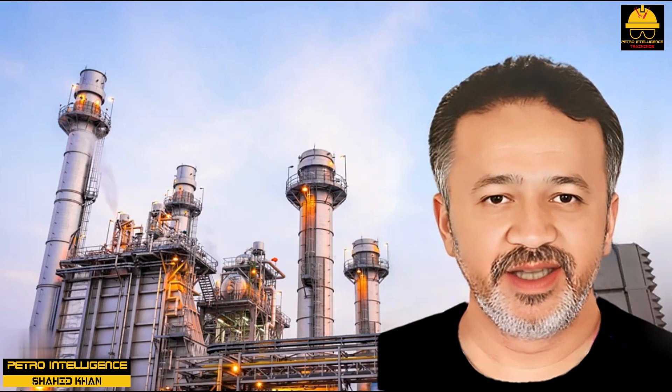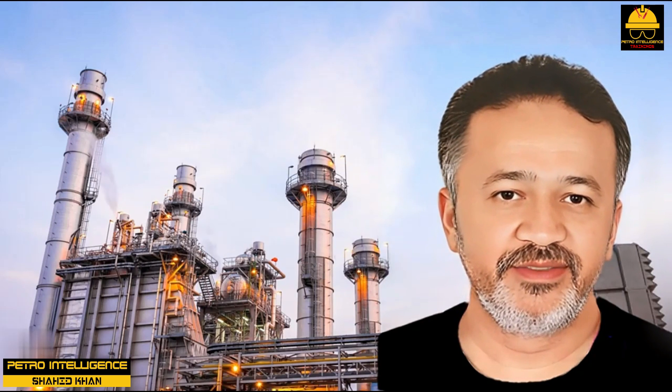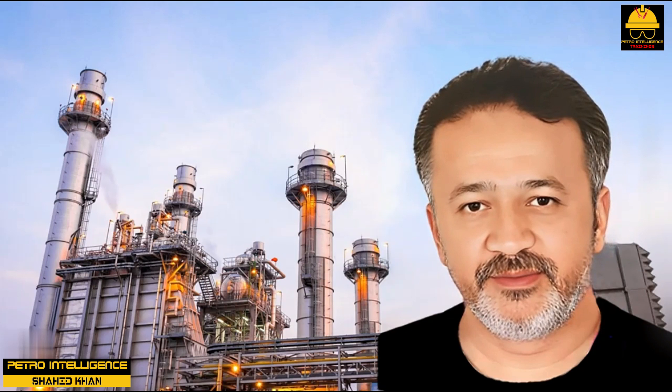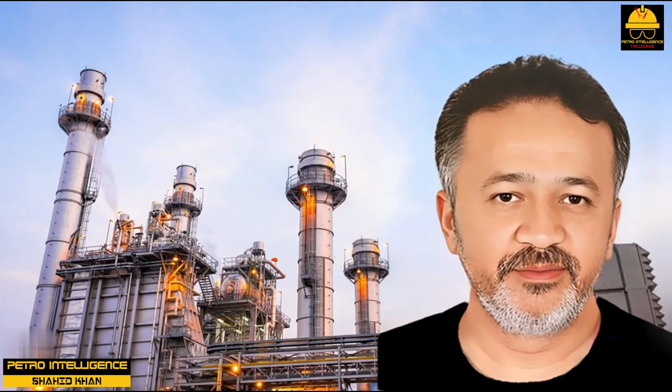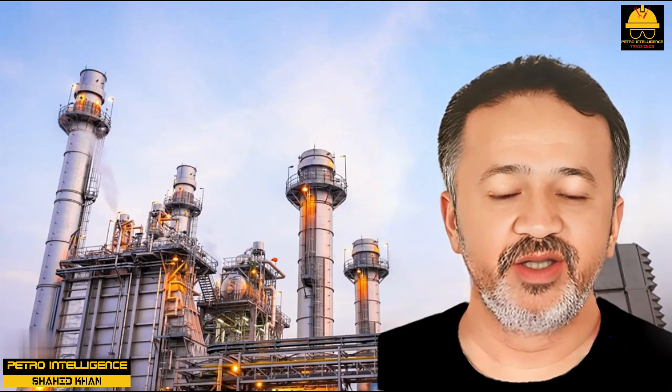An engineer had a job working in a refinery. The unit bottleneck he was consulting for was the furnace. Both the firing rate and TMT (tube metal temperature) were low. However, the tubes themselves were ordinary carbon steel — not only the convective tubes, but the radiant tubes as well, all were carbon steel. Theoretically, engineering calculations showed carbon steel was adequate. Note that the furnace specs were issued by an American contractor and not the locals. Theory is fine, but it needs to be tempered with common sense. Process heaters in refinery hydrocarbon service should employ chrome steel and not carbon steel tubes in the radiant wall and shock tubes. Carbon steel tubes should be confined to the convective section.